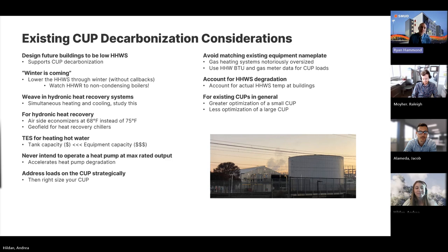Address loads on your CUP strategically. What is meant by that? All it takes is one rogue building to ruin the fun of it all. So if you have one building that's acting out of compliance, requires super hot water, requires super chilled water, it's going to ruin the fun for everyone else. So get those buildings commissioned, tidied up. If you find a rogue building on your project, you might be able to address the strainer, clean the coils. It might perform better, commission it.